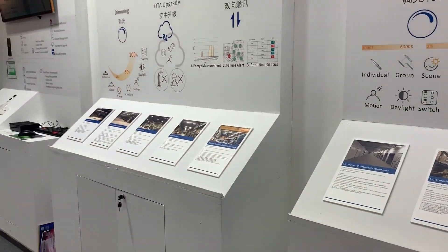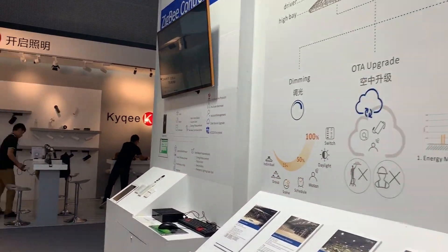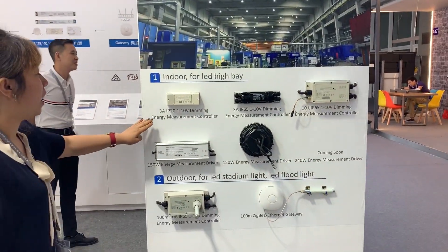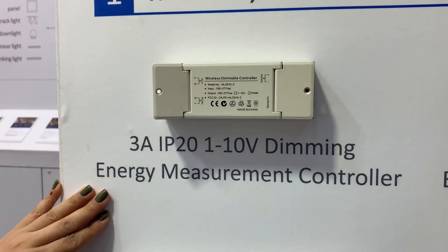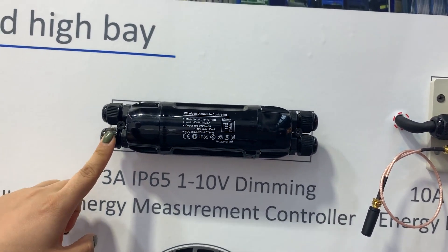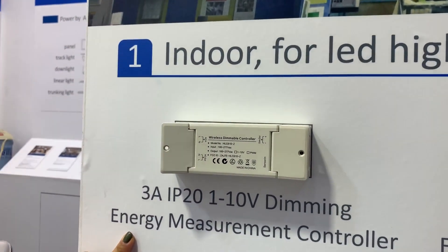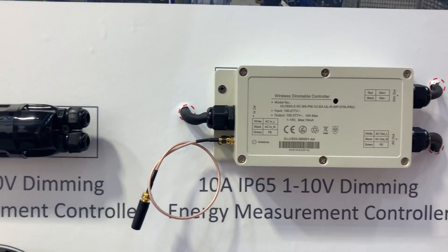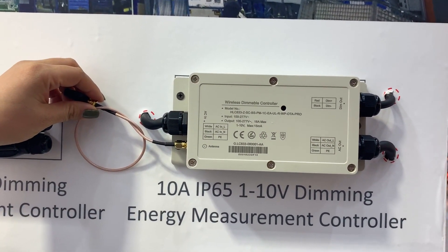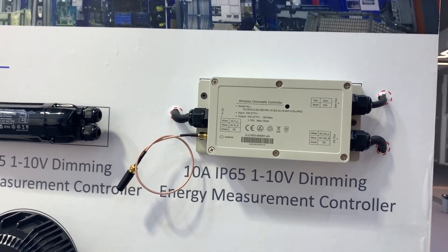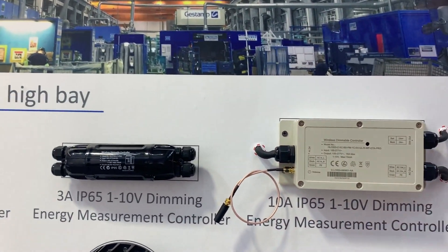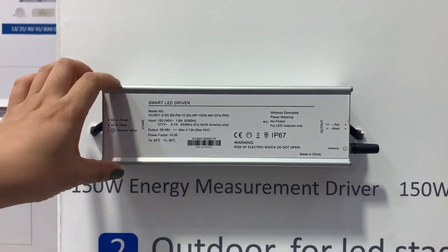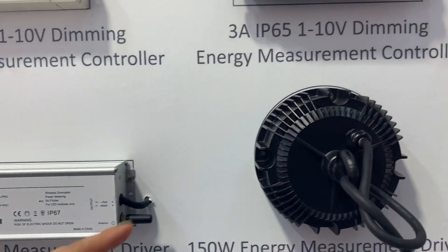These are the two application solutions we offer. Looking at the full range for industrial lighting control: there is an IP20 controller at 3A and an IP65 version. The IP65 can be placed outside the high bay fixture, while the IP20 needs to be installed inside the driver box. For high-power high bay applications, we recommend the 10-ampere IP65 dimming controller. All three support energy measurement, and we are currently developing a 150-watt driver, available in rectangular or round form.